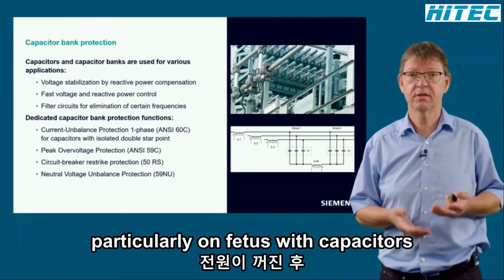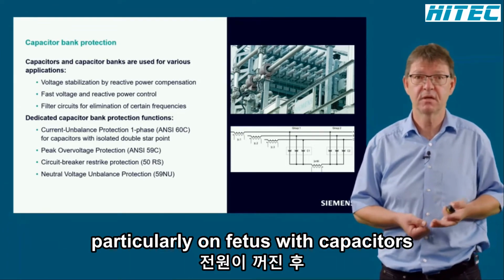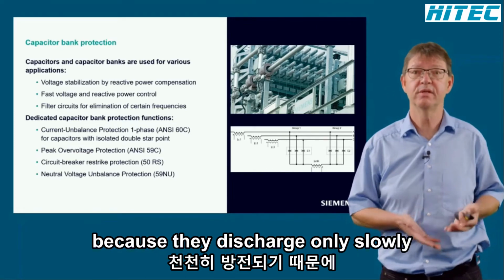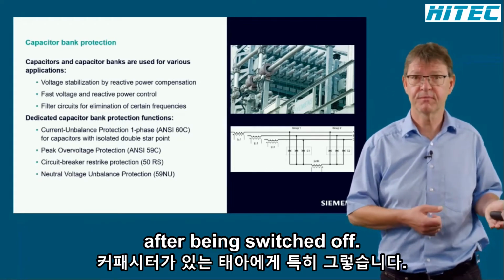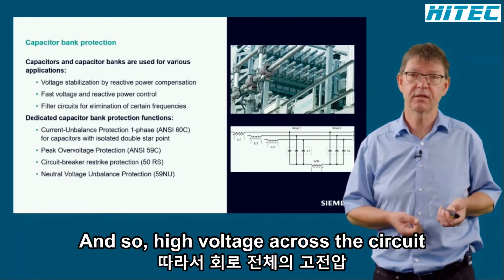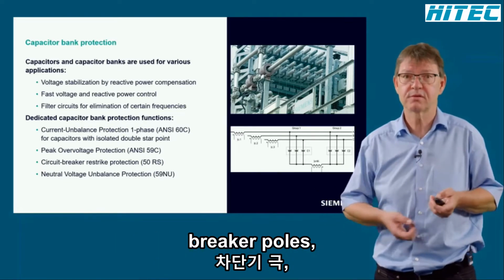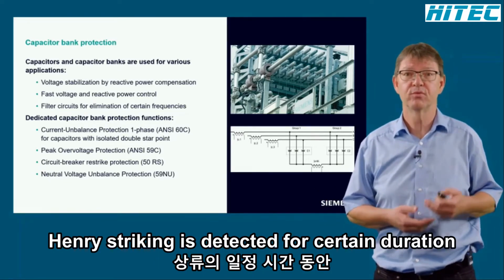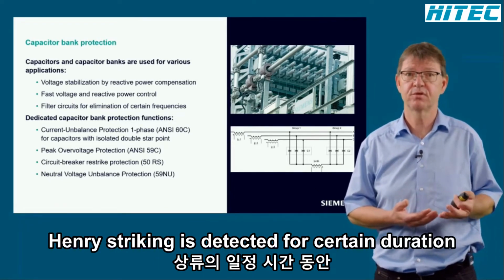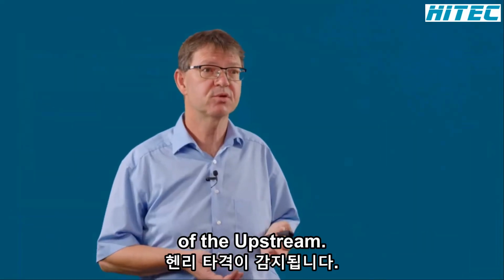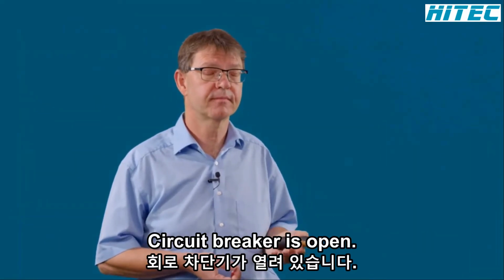This occurs particularly on feeders with capacitors because they discharge only slowly after being switched off, and so high voltages can occur across the circuit breaker poles. When restriking is detected for a certain duration, often the upstream circuit breaker is open.